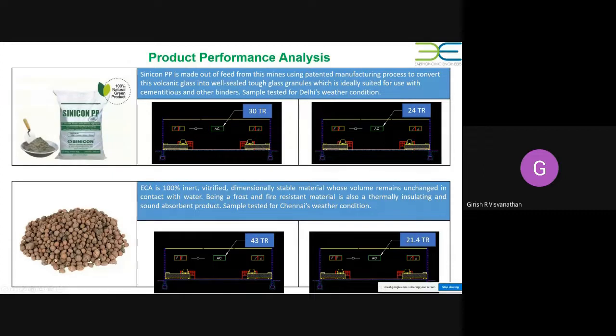There is something called expanded clay aggregate. If you put it on top of your roof, the heat reduction comes down by 50%. So what originally for a 10,000 square feet facility in Chennai would require 43 TR, by applying this product comes down to 21.5 TR. That's 20 TR into 50,000 rupees, about 10 lakhs of savings, whereas the product might have cost only 2 lakhs, passing on a benefit of 8 lakhs to the owner. Plus, the cost of operating 43 TR is double the cost of operating 21 TR. So you not only save on capital investment, but also on operational costs. This mapping is very important to estimate how green your building is.